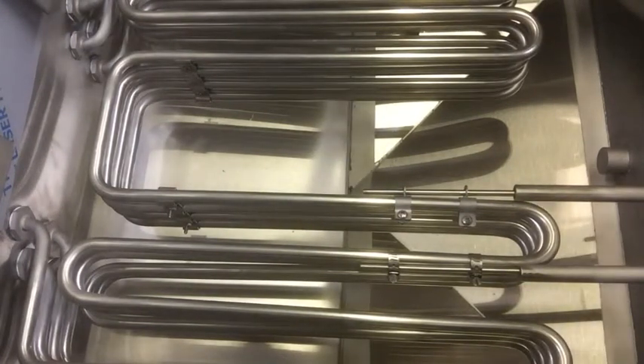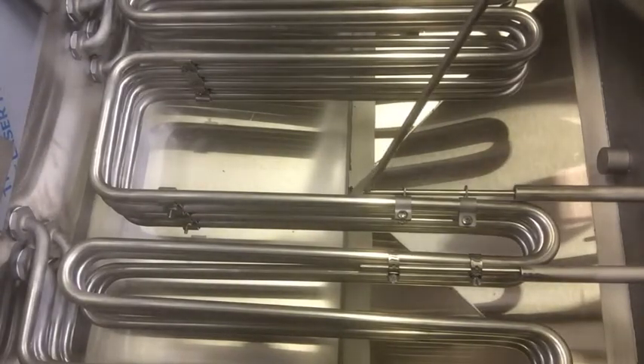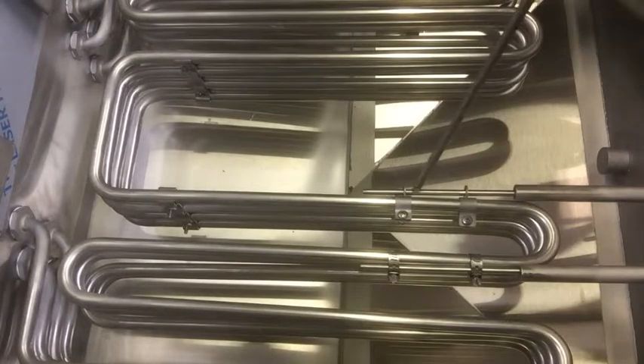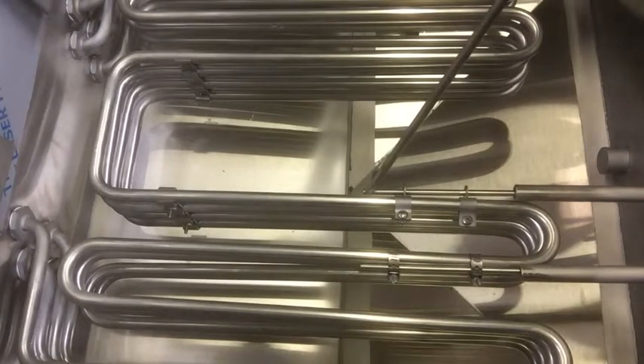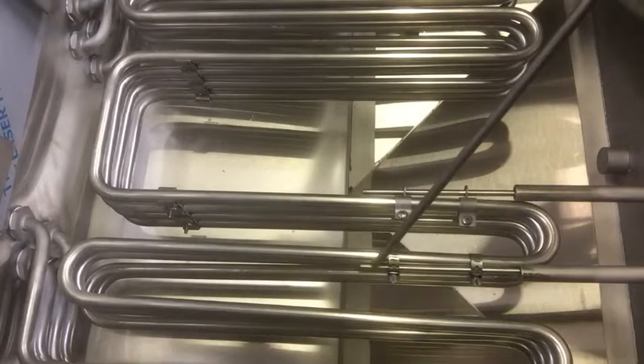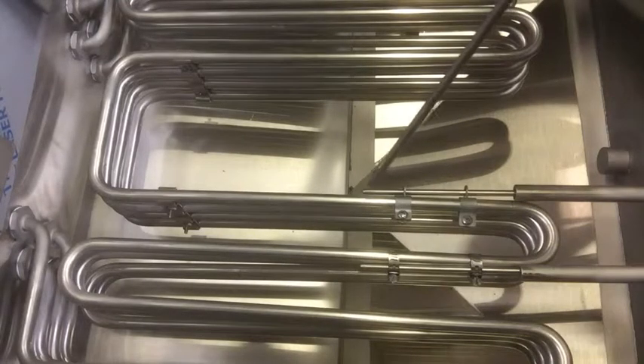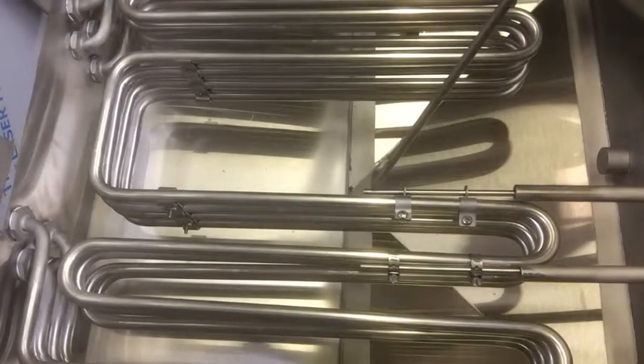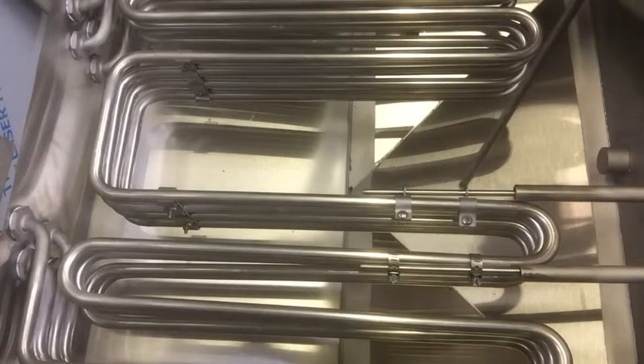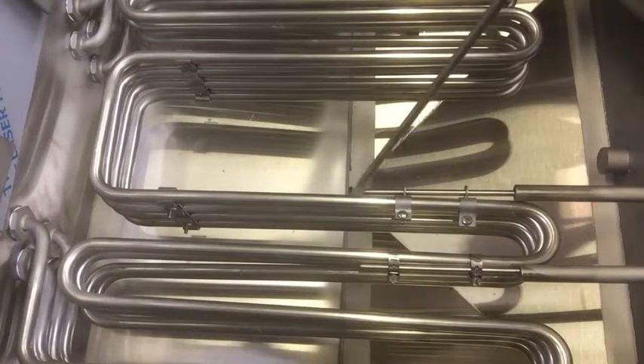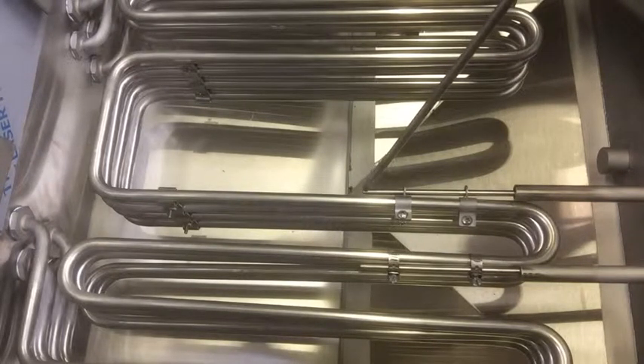The inside of the fry vat. Got the element brackets, which hold the elements apart. Right here we have our high limit probe. We have an element probe here as well, and you can tell the two of them apart because the high limit probe goes through these brackets. It's got these little washers that are welded to these clamps, and it holds it away from the element. So it's actually sensing the oil temperature.